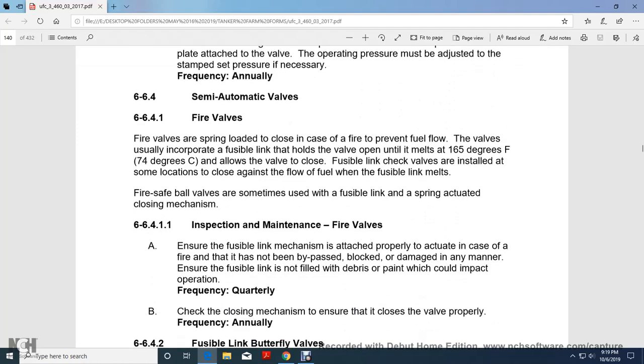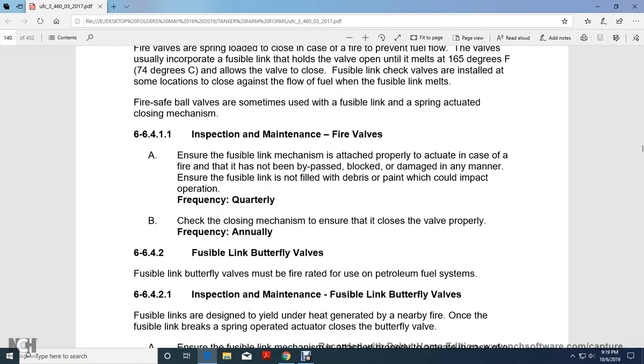Semi-automatic valves. Fire valves are spring-loaded and closed in the case of a fire to prevent fuel flow. The valves incorporate a fusible link that holds the valve open until the link melts at 165 degrees, allowing the valve to close. Fusible link check valves are installed in some locations against the flow of fuel and close when the fusible link melts. Fire-safe ball valves are sometimes used with fusible links and spring-actuated closing mechanisms.